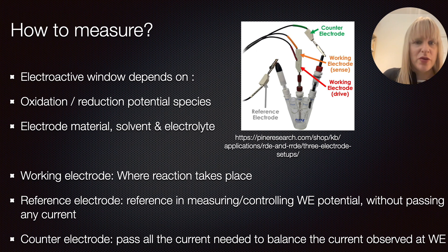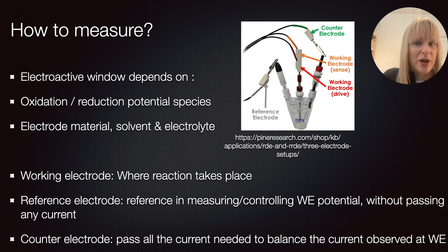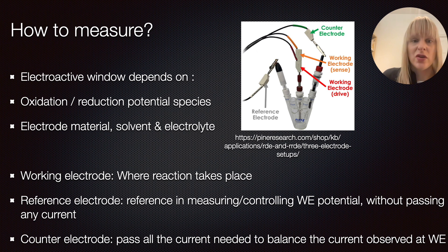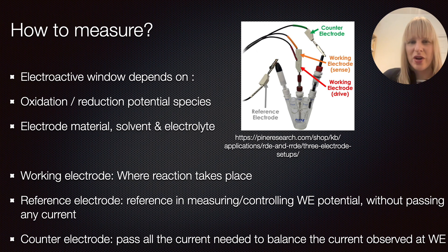The counter-electrode is also important because it needs to close the system — it passes all the current needed to balance the current observed at the working electrode. One of the fiddly things is that these three different electrodes can't touch each other, otherwise you get a short circuit. So you might want to work with a specifically designed custom glass cell. Alternatively, I work with screen-printed electrodes where you can have the reference and counter-electrode integrated onto the system itself, which makes it easier to go smaller. In that case, you can measure drops of liquid, which is important for sensing real samples at very small volumes.